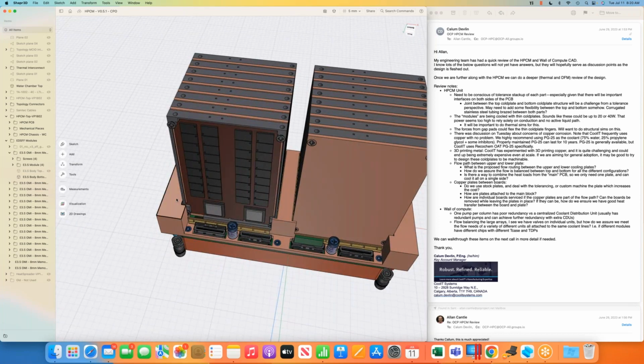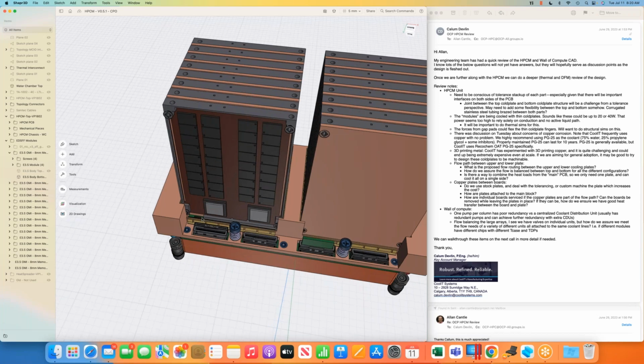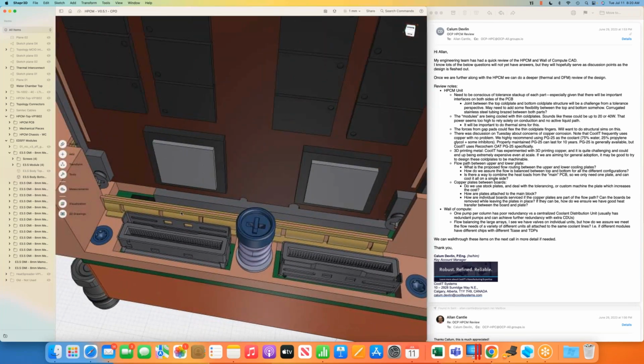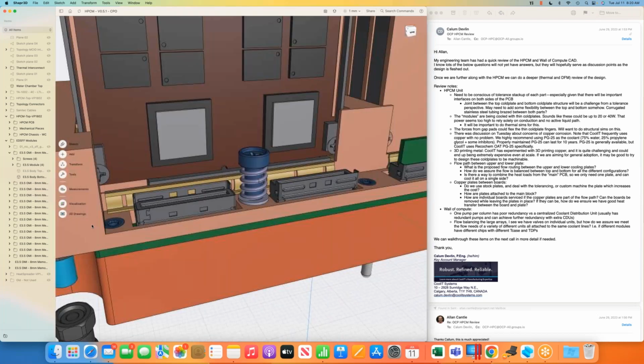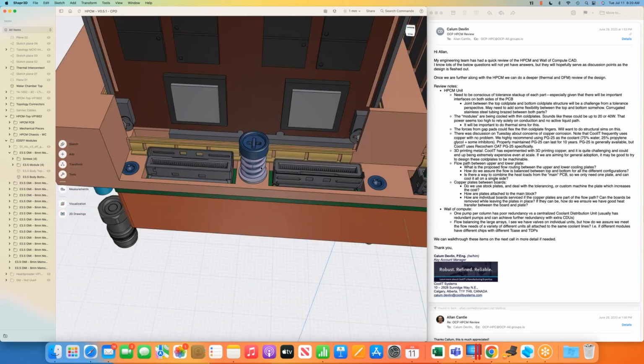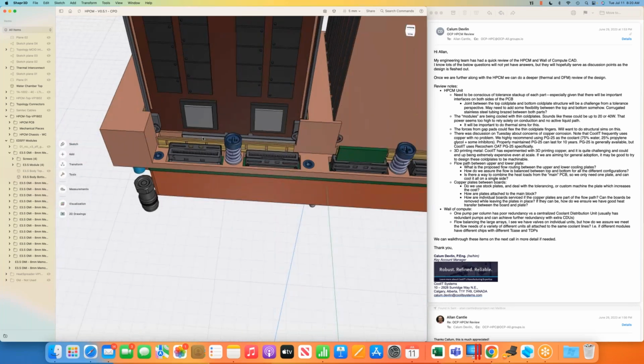And in this, this would be a copper lid, and we would conductively cool down to it. This is what we're thermally modeling at the moment: we'd have some sort of thermal coupling between the actual module itself and this copper plate, and this copper plate would have the water flowing up the vanes between the modules, so you'd have water directly attached to these cold plates. So you would conductively cool that, and Ender, I don't think Ender's on the call, but he's currently thermally modeling that for us.